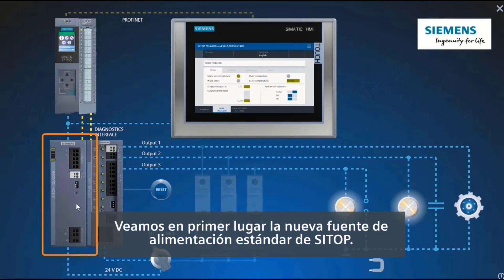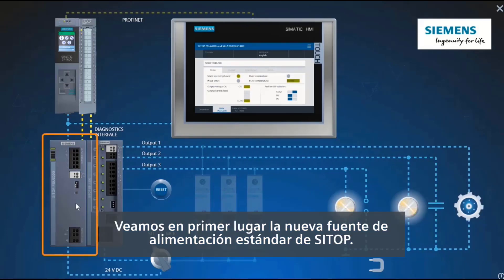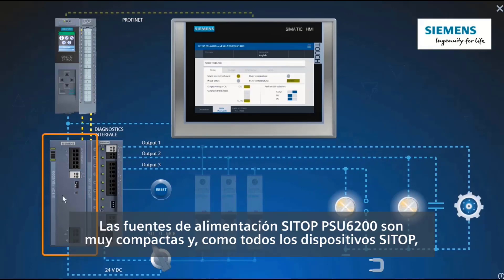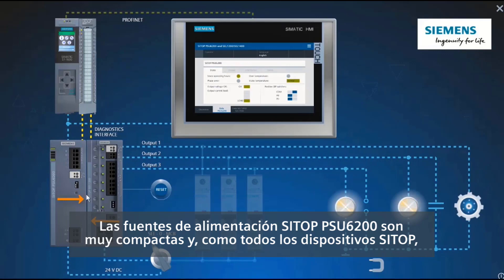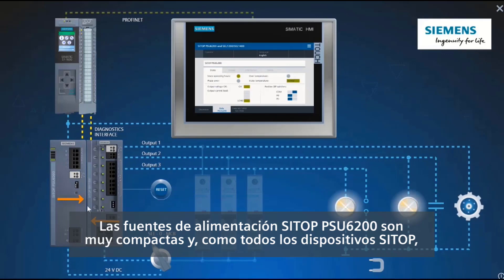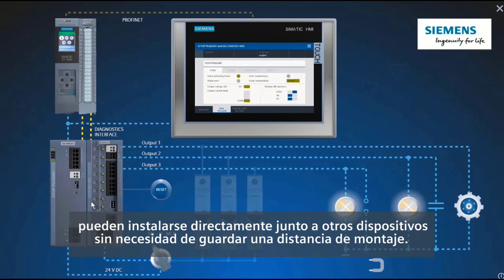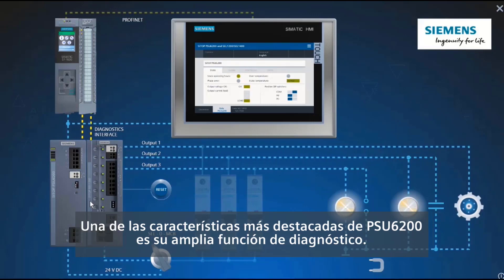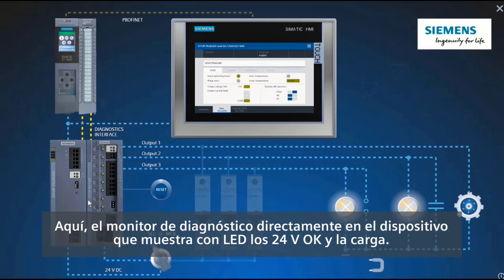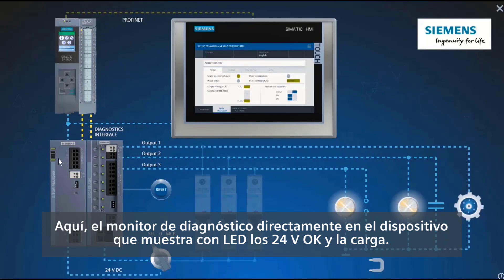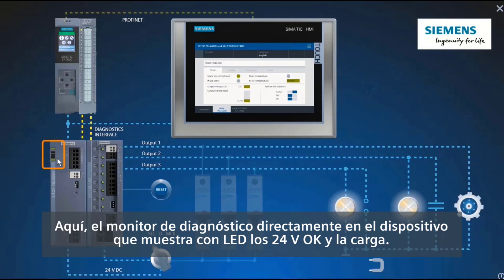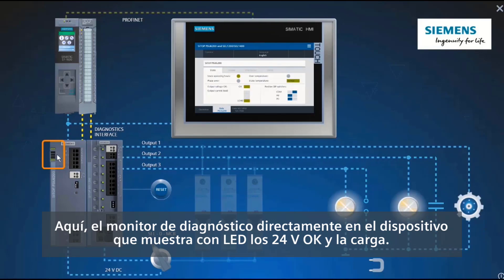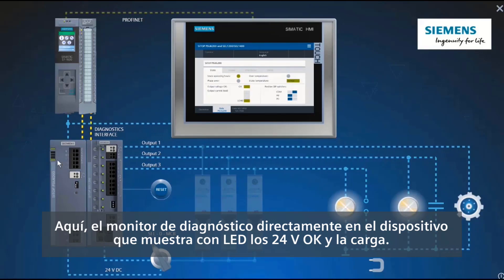Let's turn first to the new SITOP standard power supply. The SITOP PSU6200 power supply units are extremely compact and, like all SITOP devices, can be installed directly adjacent to other devices without any spacing. One of the highlights of the PSU6200 is its extensive diagnostics function. Here is the diagnostics monitor mounted directly on the device, which uses LEDs to indicate the loading and the 24-volt OK signal.